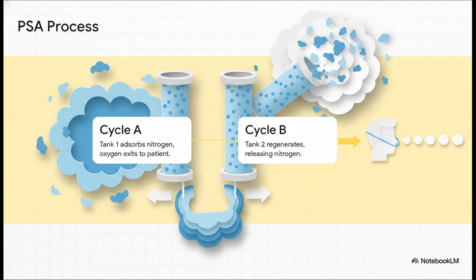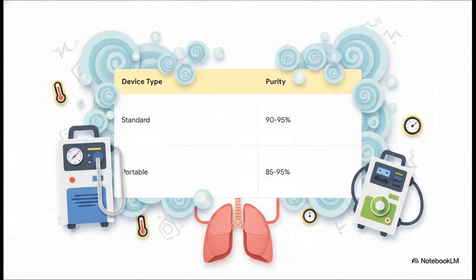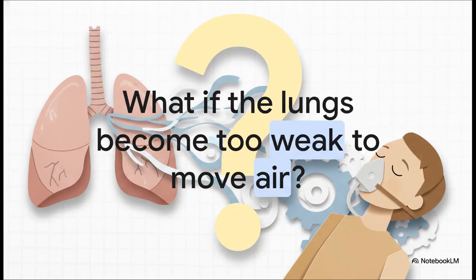It is wild. And the result of this mechanical breathing rhythm is incredibly impressive. Standard and portable concentrators can take that basic 21% room air oxygen and boost it to an intensely pure 85 to 95% output. Plus, the machine is continuously monitoring its own pressure and temperature just to guarantee that this life-sustaining purity never, ever drops. But let's take this explainer to the next level.